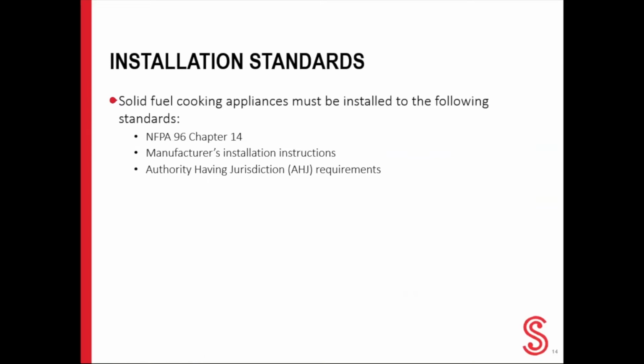So what are the standards that should be followed when installing a solid fuel appliance? NFPA 96 is the standard from the National Fire Protection Association that provides fire safety requirements intended to reduce the potential fire hazard of public and private commercial cooking operations. More specifically, NFPA 96, Chapter 14, Solid Fuel Cooking Operations, provides the safety requirements for solid fuel cooking, and that includes exhaust venting, location of appliance, air movement, fire extinguishing equipment, procedures for inspections and cleaning, the maintenance of the appliance, as well as the minimum safety requirements for fuel storage, handling, and ash removal.